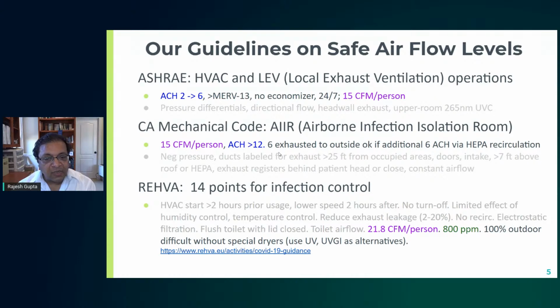The European standard REHVA has many different measures to reduce risk, but again, it comes to the flow rate of 21.8, which is basically the translation from metric to imperial units. And of course, we often look into estimating the amount of fresh air by estimating the amount of carbon dioxide in a space. So oftentimes people would monitor just the amount of carbon dioxide as a proxy for how much rebreathing there is in a room.